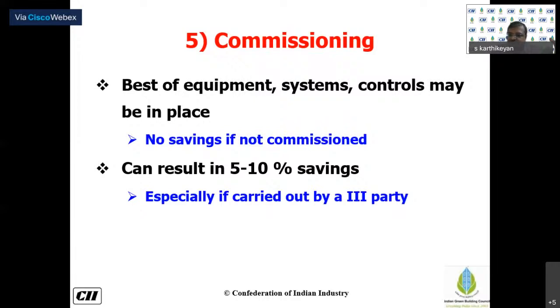That's why we insist on commissioning, where a third party comes to verify and study the equipment, do an energy audit, and determine the original design performance versus the present performance, the deviation, and the reasons for it. Knowing the reasons for deviation allows you to take corrective measures and improve equipment performance.